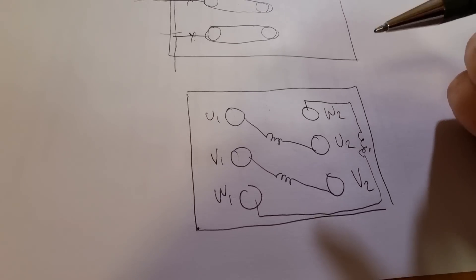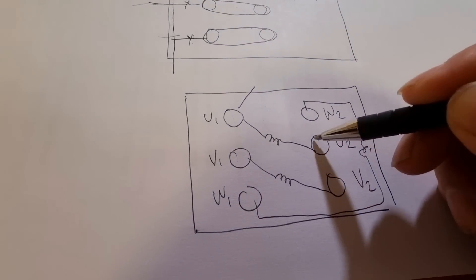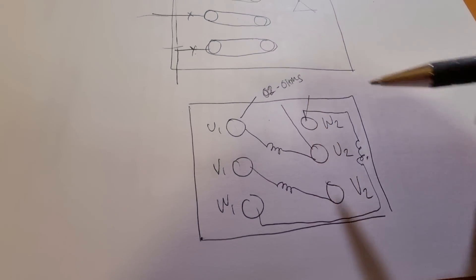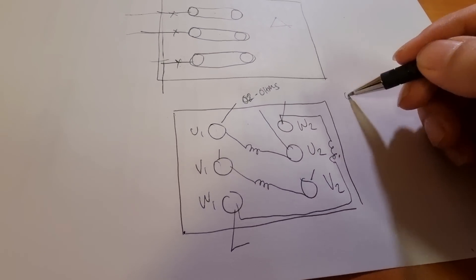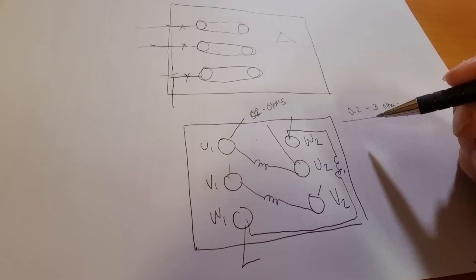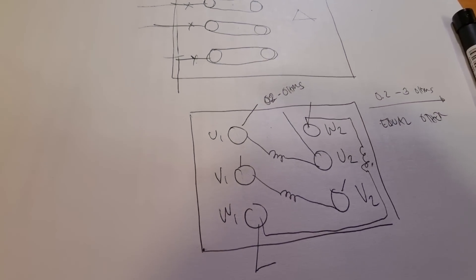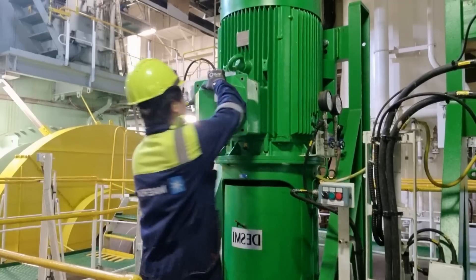To measure the winding resistance and the condition of the winding, place the tester probes across each winding pair and you should get a good continuity reading of around 0.2 ohms. Check each combination — this and this, and this and this — with your multimeter. If you get values in the range of 0.2 to 0.3 ohms, those are good values and they should all be equal to each other. After checking, our system is in good condition.